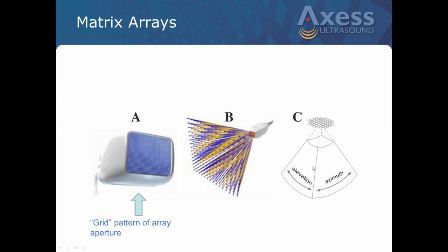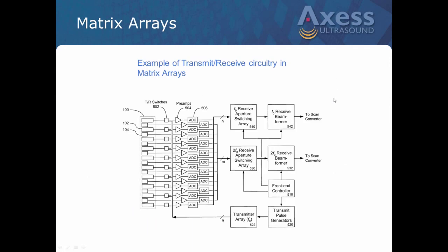Now this gives you a little bit of an example of some of the electronic controlling, and this is by no means totally comprehensive, but here's your transmit receive switches, and these are all multiplexed, so they're all timed out, and this is what controls those matrix single crystal arrays and allows the system, with its knowledge, to control the sequence of send-receive so that you can get that image quality improvement by the way it fires and receives the ultrasound beam.